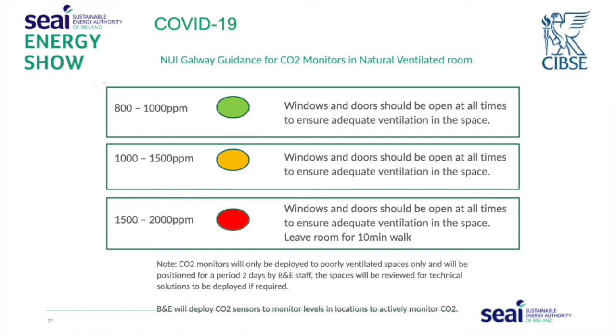Again, it's about using and operating these and setting the limits. These are the limits that basically we've been working on, the same limits that are in other guides as well. So 800 - well, outside is 400 parts per million - 800 to 1,000, keep all the windows and doors as they are; 1,000 to 1,500, the windows and doors should be open at all times to ensure adequate ventilation; and then 1,500 to 2,000, open it up, go for a walk and come back. The sensors go up and down very quickly once there's a bit of fresh air movement.